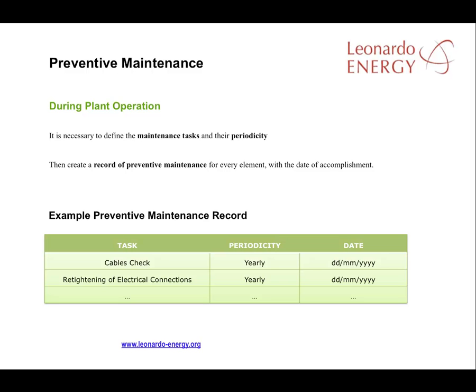In designing a preventive maintenance program, it's important to define the maintenance tasks and how regularly they should be carried out. Those tasks, their frequency and dates for accomplishment should be defined in a table that will also provide a log of progress on each task. A more complex table could include notifications or alarms from the monitoring system and a column for the latest date by which a task must be done.